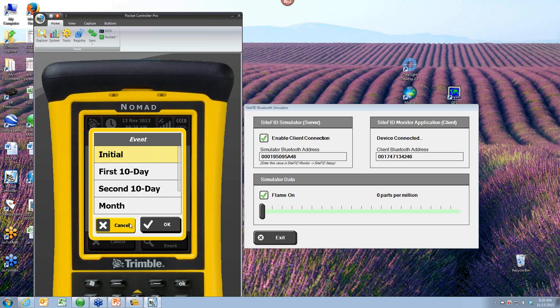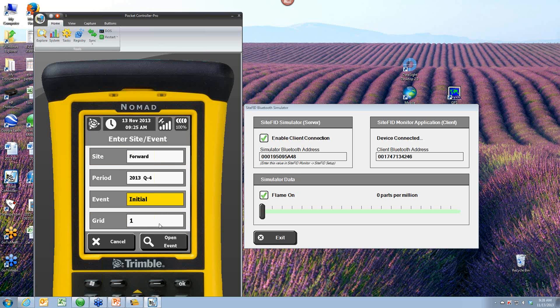And then our grids. So you can have hundreds of grids. What you can do is set up, and not all grids go 1, 2, 3, 4, 5. You can go from grid 5 to grid 20 to grid 30. But each time you go to a new grid, you pull up in the software and tell it which grid you're in so that it can follow you, and that's where the mapping really helps as well.